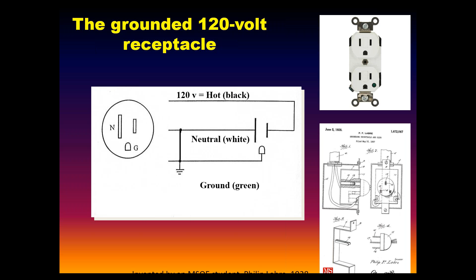And this is the stuff that we've been doing since the beginning of time. What we continue to do, and this is a good thing to do, so I'm not in any way suggesting you stop doing this, is the ground wire continuity test, what you do with your safety analyzers, if you can find a ground point on the machine. We want to continually verify that the ground pin is indeed electrically connected to the case of the device, if you have a conductive case. So this is what we've been faithfully measuring since the beginning of our time.